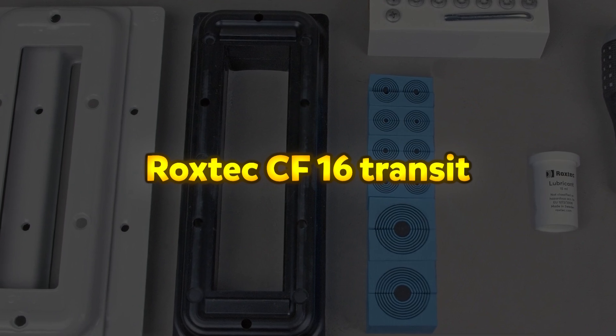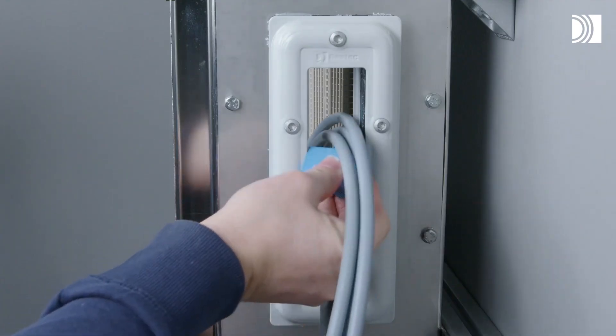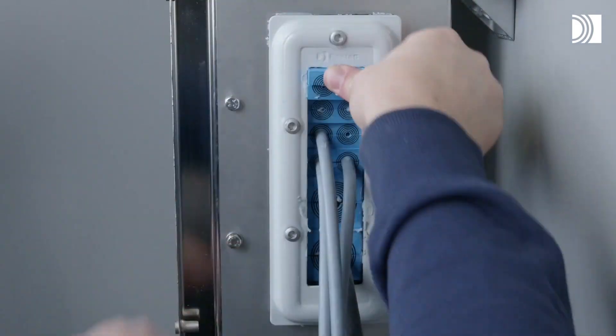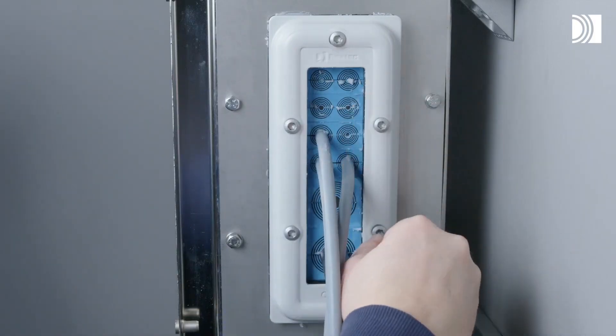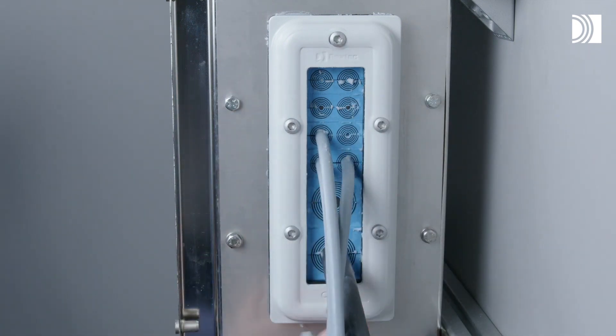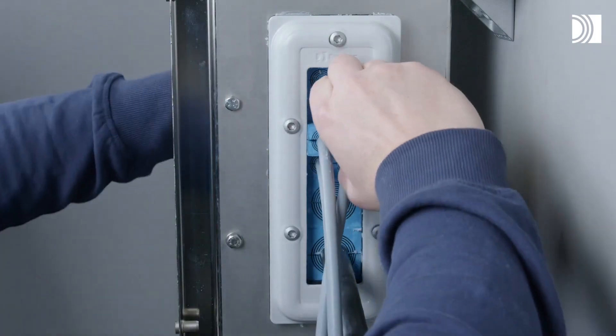Roxtec CF 16 Transit. The Roxtec CF 16 is a high-performance cable entry seal designed for enclosures, offering a low-profile metal frame that ensures a secure and efficient cable transit solution. It is available in both powder-coated mild steel and stainless steel, with the stainless steel version rated to IP69K, providing superior protection against dust, water, and high-pressure cleaning.